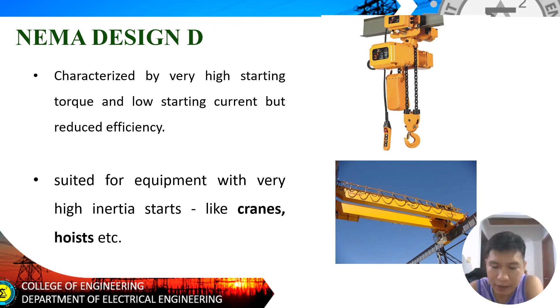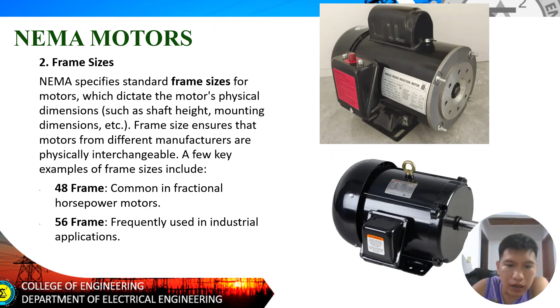So, NEMA motors, frame sizes. NEMA specifies standard frame sizes for motors which dictate the motor's physical dimensions such as shaft height, mounting dimensions, etc. Frame size ensures that motors from different manufacturers are physically interchangeable. A few key examples of frame size include the 48 frame, common in fractional horsepower motors, and the 56 frame, frequently used in industrial applications. Okay? So, yan yung mga frame size ng ating mga motors. Sa laboratory natin, I think meron din tayong motor doon na ginagamit.